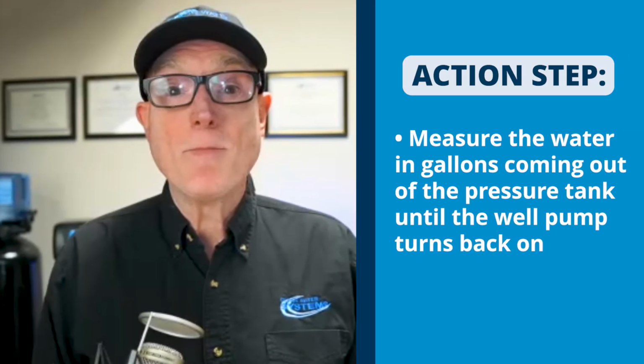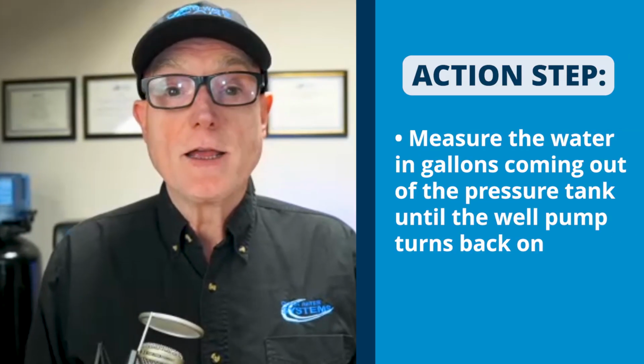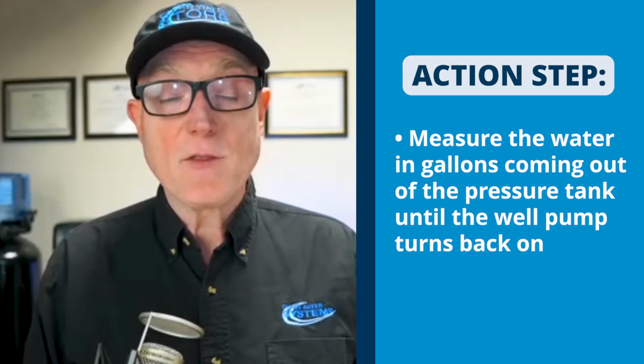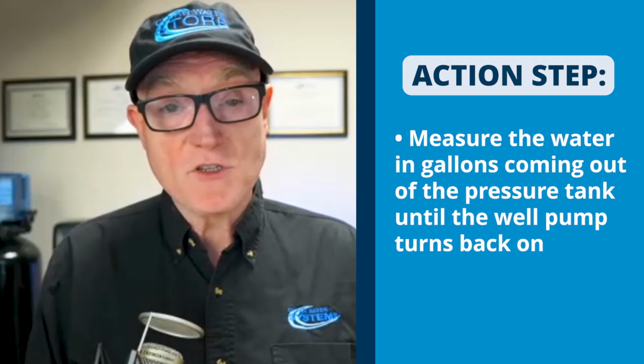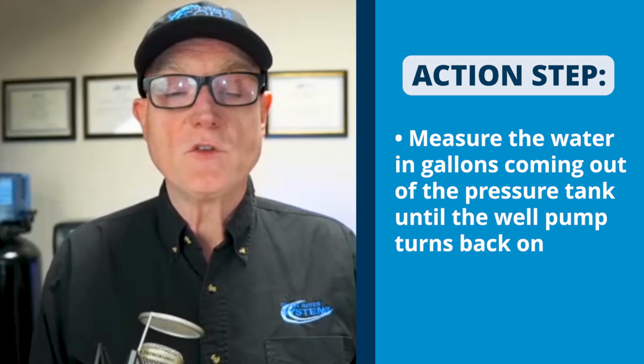The next step is to measure the water in gallons coming out of the pressure tank until the well pump turns back on. So what you would do is get a 5-gallon bucket and a hose bib and garden hose, or you could do it in a sink too, but usually somewhere around the pressure tank, there's often a hose bib.